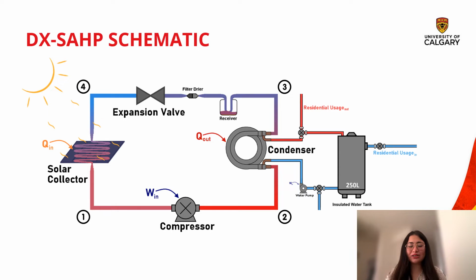Now let's talk about the technology itself. On the screen here is a simplified diagram of the thermodynamic cycle and the key system components. The system is comprised of 4 primary components: an evaporating unit, comprised of a solar thermal collector; a compressor; a complete condensing unit, comprised of a coaxial condensing coil, a water pump, as well as an insulated recirculation water tank; and finally, to complete the cycle, an electronic expansion valve.